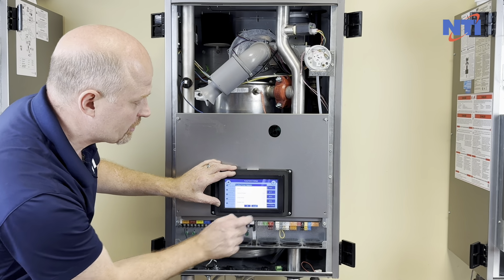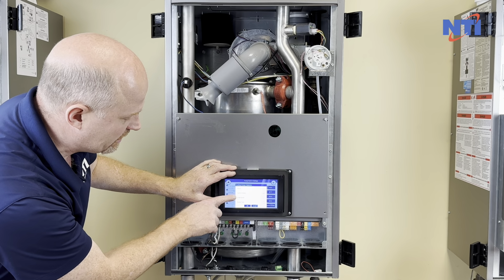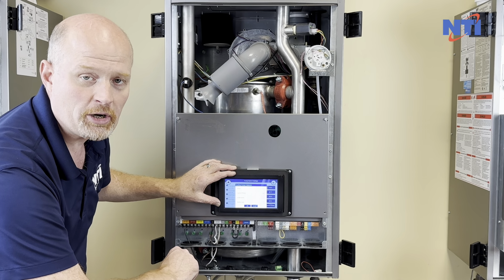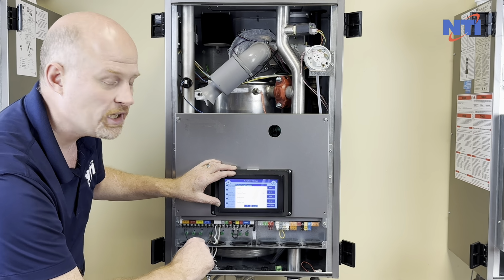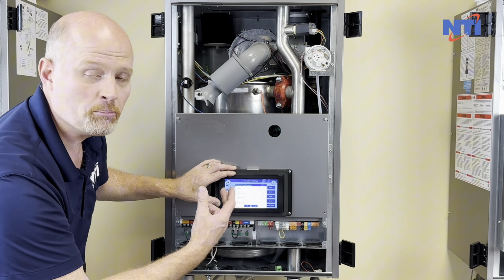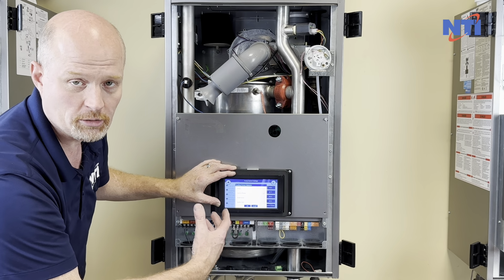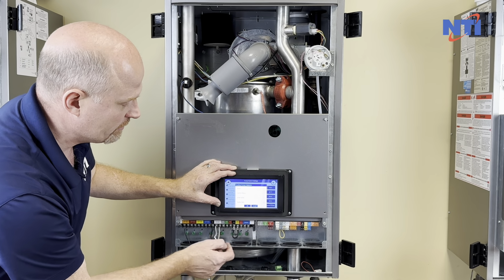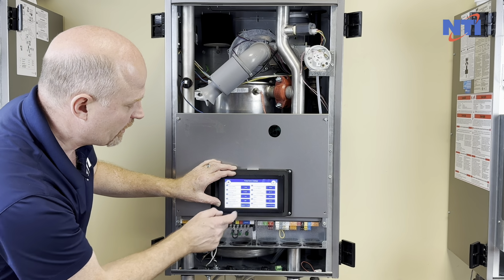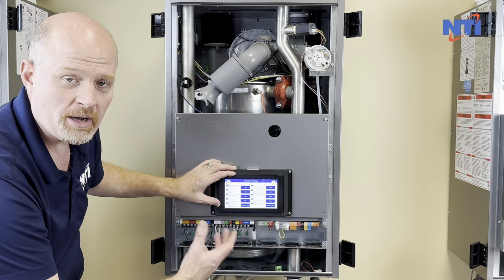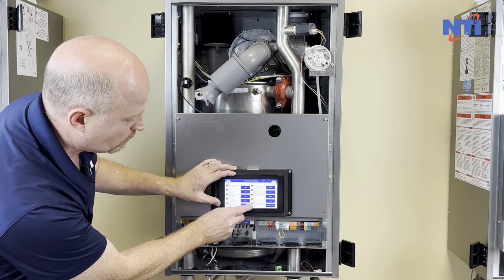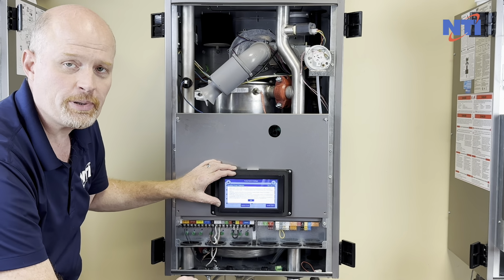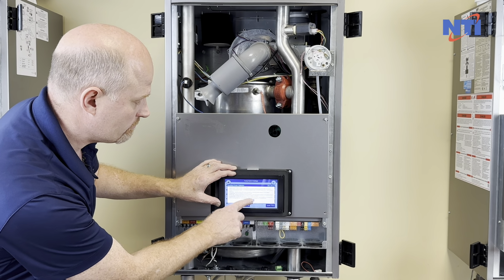Auxiliary Pump 2 selection gives you the options of system pump, DHW recirc, and buffer. So there is a little redundancy. You could use either pump output for the system pump. You cannot use the system pump on both outputs at the same time because they'll both work at the same time. So you do want to set different functions on different pumps. If at any time you're confused and not sure what the pump selection will do, find these little blue I buttons and touch that, and it gives you a description of what each pump does and when it operates.